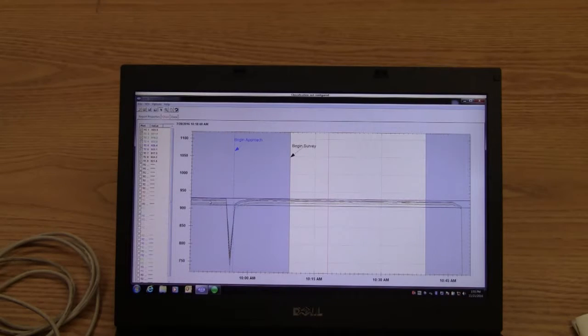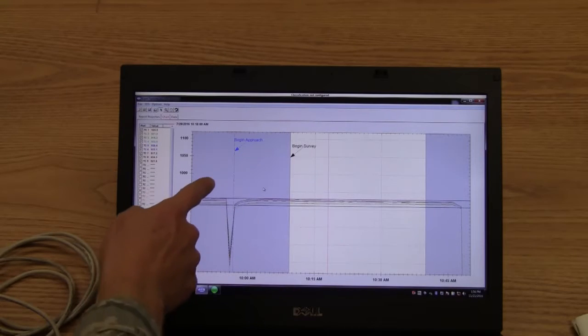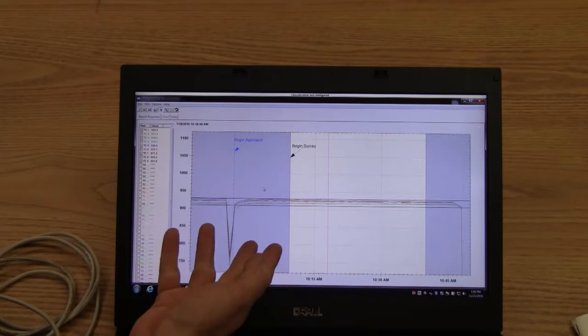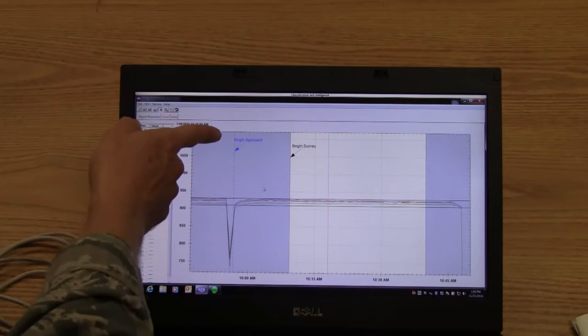What you're seeing here is I brought my oven up to temp. I let it run for a little while to stabilize. Once I was sure it stabilized, then I performed, just for the purposes of doing a pure TUS survey, a simulated parts load. So what that means is I already had my rack in the oven, my simulated parts load, I open my door, you have your huge temperature drop, put the part in the oven, right, simulated, close my door, and then begin my approach.